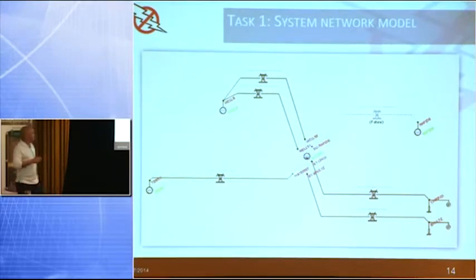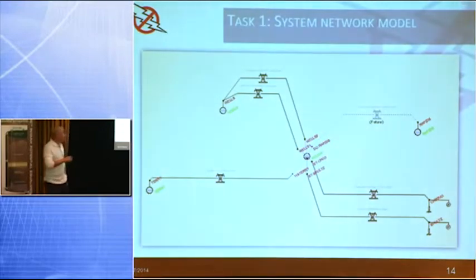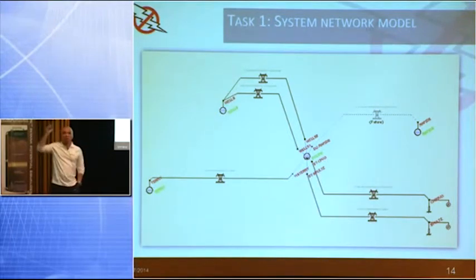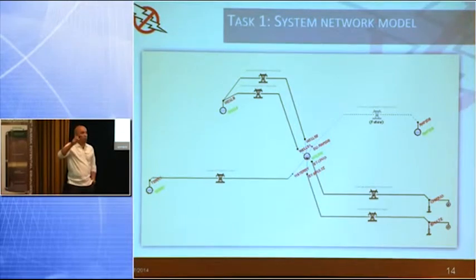What this represents here is the ground under test, let's say the facility that we're looking at, actually represented by this icon. This then represents the transmission lines of the system, not just the ground system that we're testing. Because if you think about it, all of these transmission lines, what are they, essentially? You have these huge metal towers, and each one of them has a ground rod, or multiple ground rods, and they're interconnected by usually a shield cable over the top. So that's all part of your electrical network, or your system.